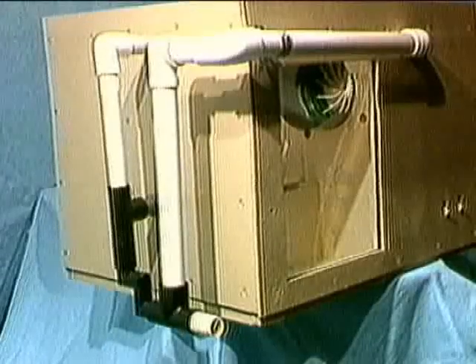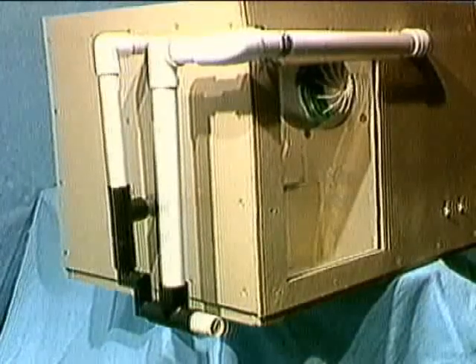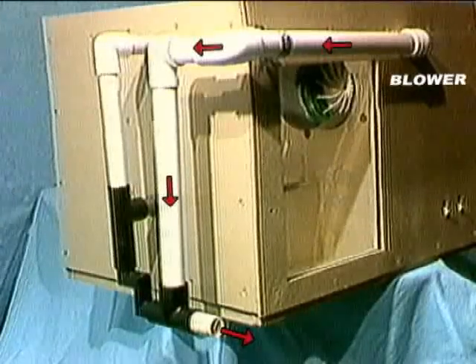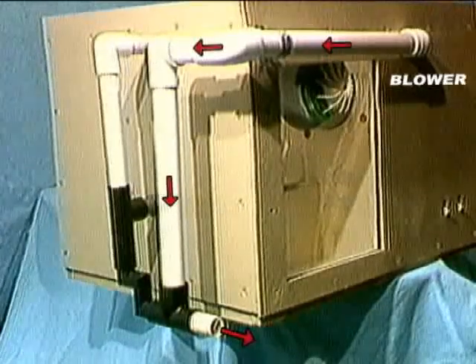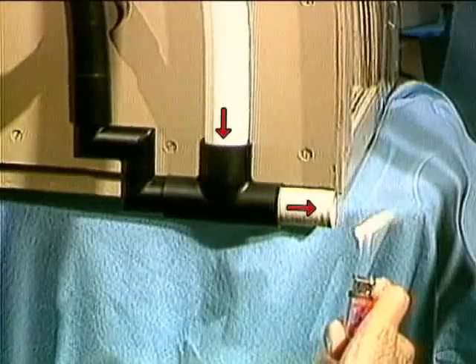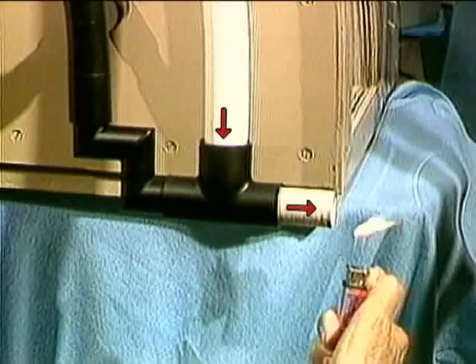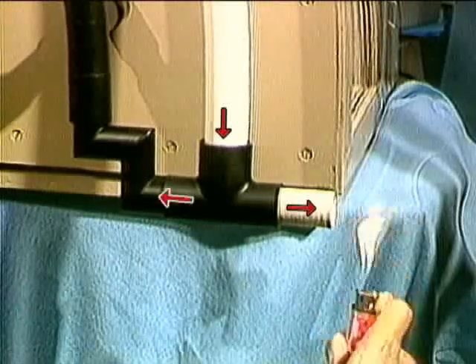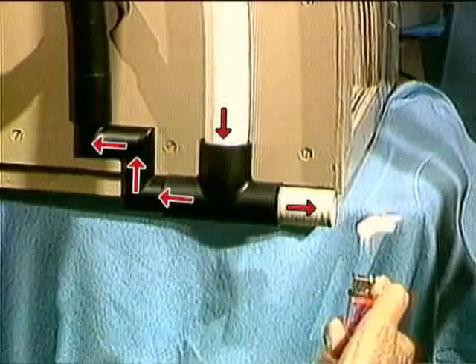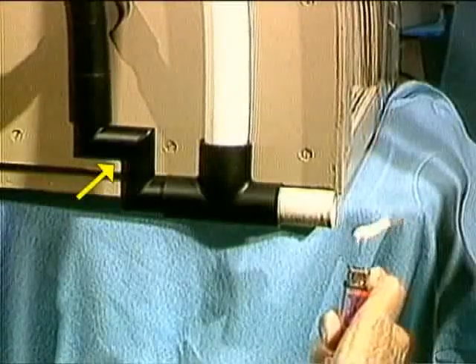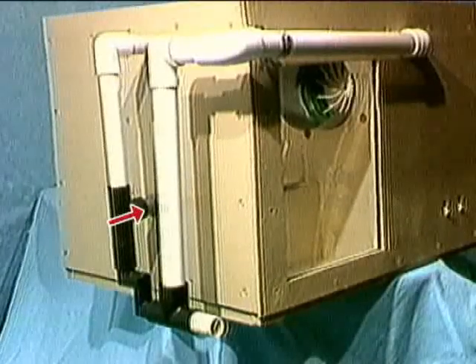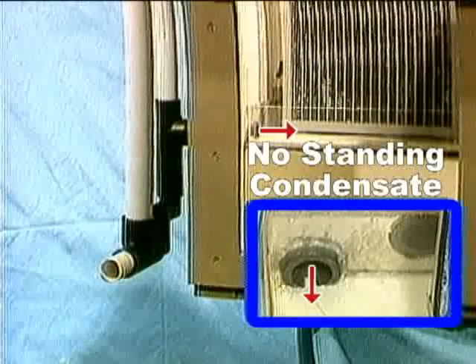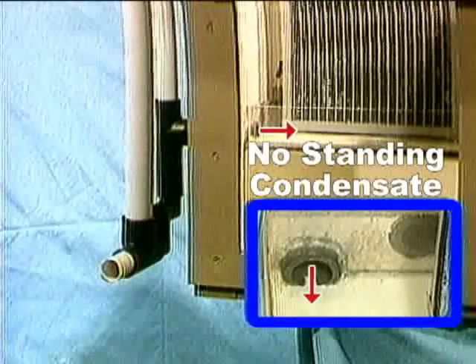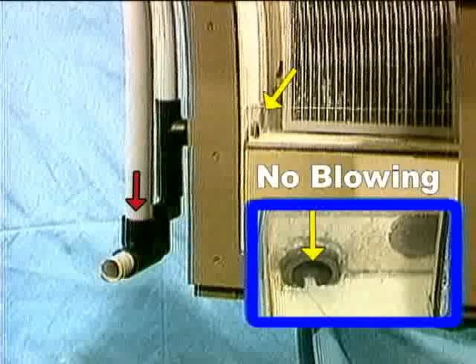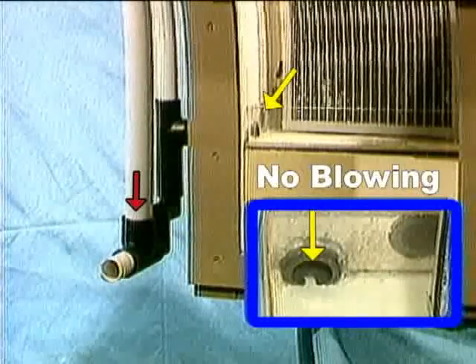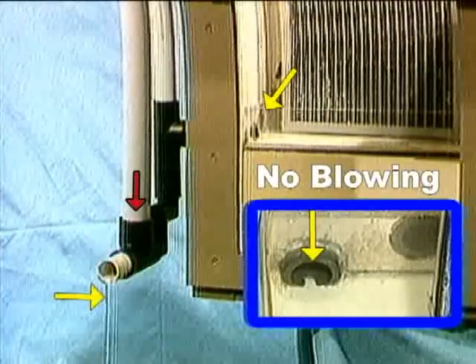The CostGard Condensate Drain Seal prevents the ingestion of outside air by taking a small quantity of air from the positive pressure side of the blower. A portion of this air is discharged to the condensate drain pipe to ensure that outside air and pollutants are not drawn into the system. The remainder of the air is directed through the mitered elbows into the air conditioning unit. The air pressure loss in these elbows ensures that the air velocity entering the condensate drain pan is too low to allow condensate to stand in the pan and cause condensate blowing. Fresh air forms the seal during all operating conditions. See how condensate flows freely from the drain pan.